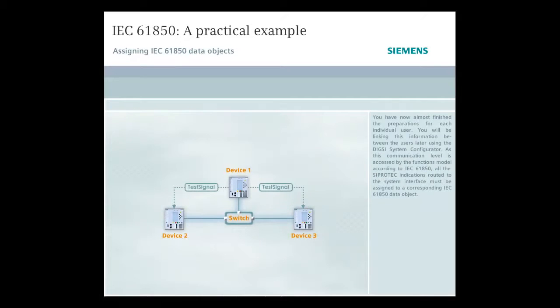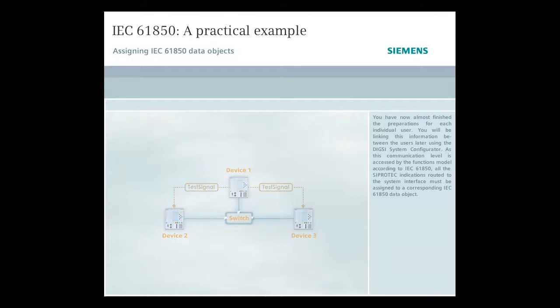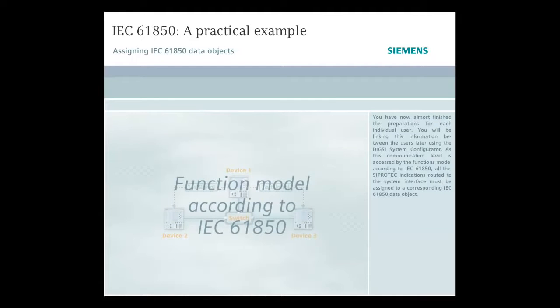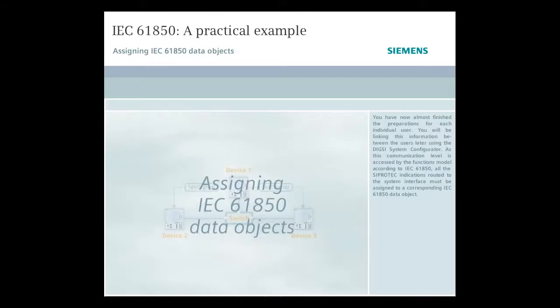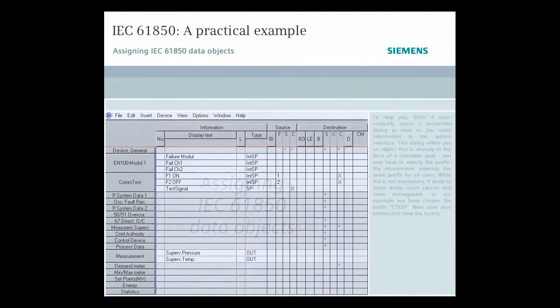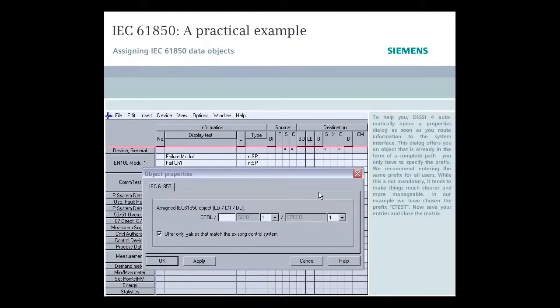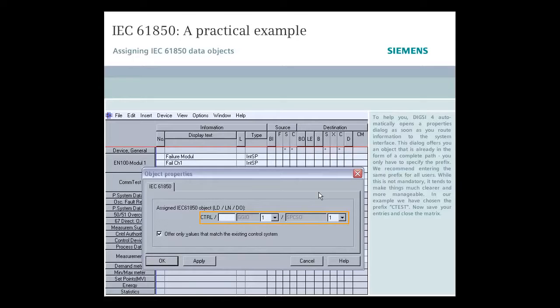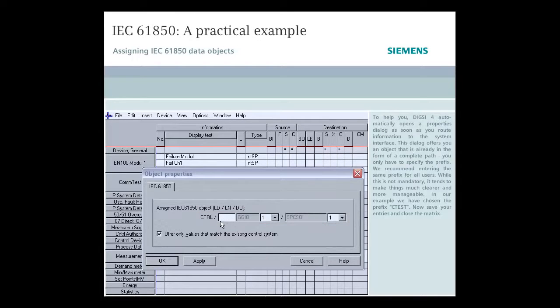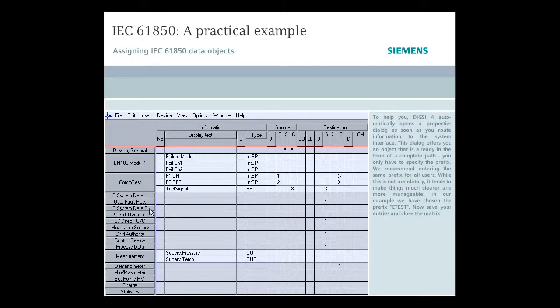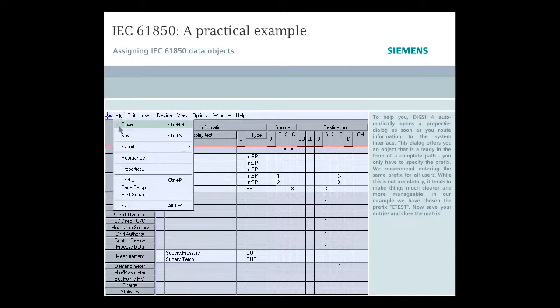You have now almost finished the preparations for each individual user. You will be linking this information between the users later using the DIGSI system configurator. As this communication level is accessed by the functions model according to IEC 61850, all the SIPROTEC indications routed to the system interface must be assigned to a corresponding IEC 61850 data object. To help you, DIGSI 4 automatically opens a properties dialog as soon as you route information to the system interface. This dialog offers you an object that is already in the form of a complete path. You only have to specify the prefix. We recommend entering the same prefix for all users. While this is not mandatory, it tends to make things much clearer and more manageable. In our example, we have chosen the prefix CTEST. Now save your entries and close the matrix.